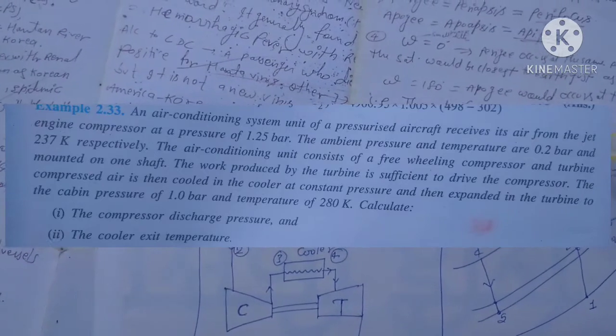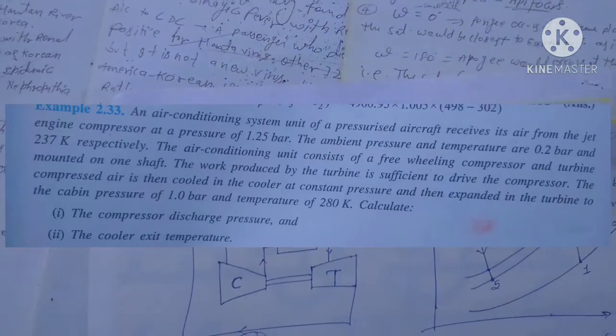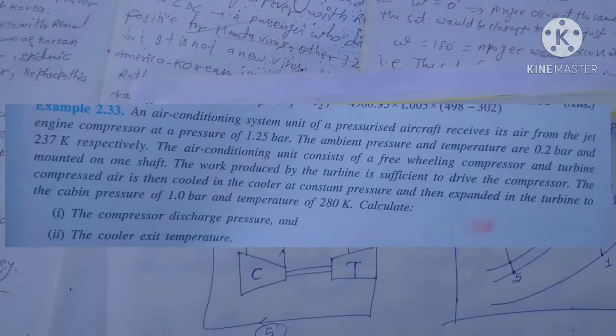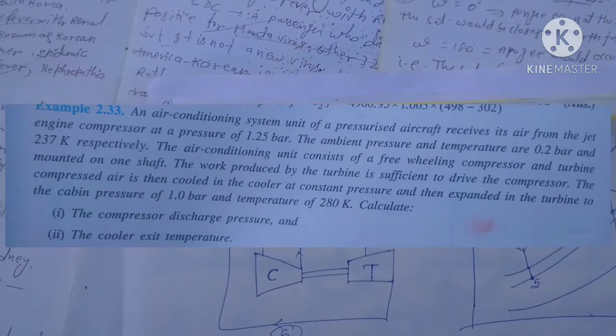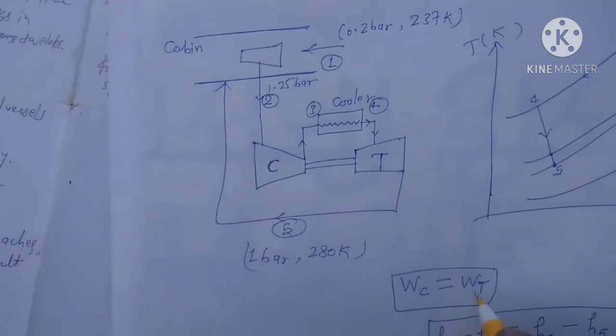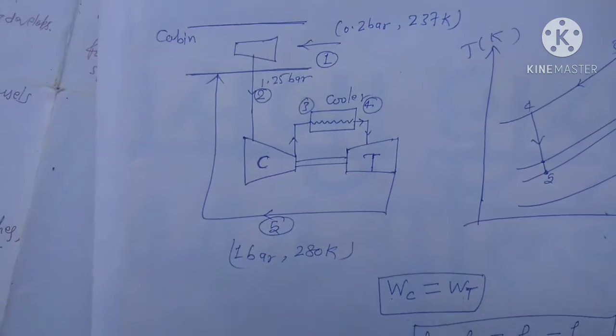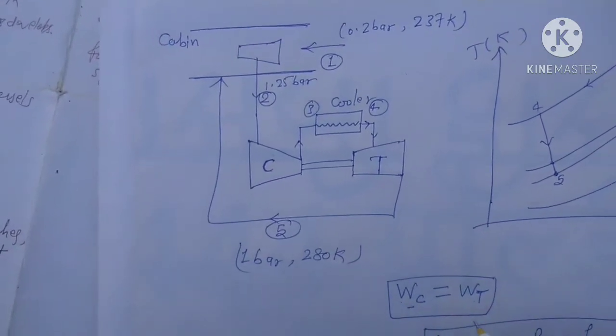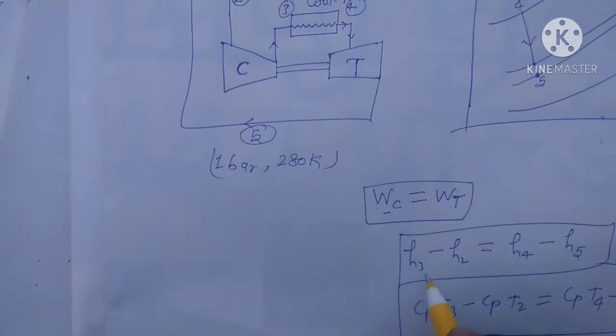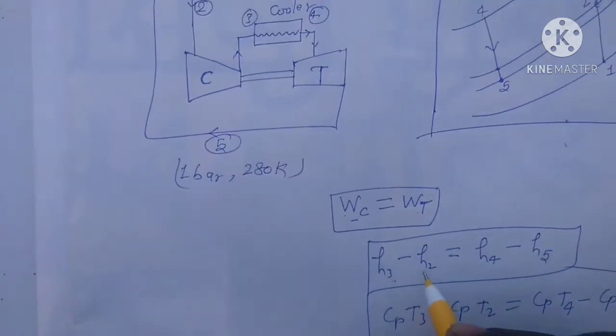The air conditioning unit consists of a free-wheeling compressor and turbine mounted on one shaft. The work produced by the turbine is just sufficient to drive the compressor, meaning work of compressor equals work of turbine. So enthalpy at state 3 minus state 2 equals state 4 minus state 5.